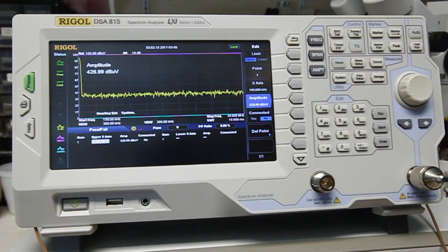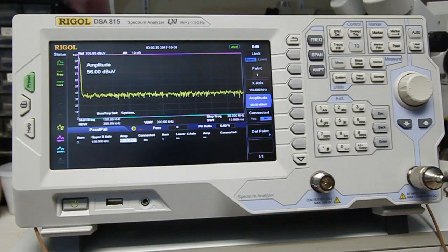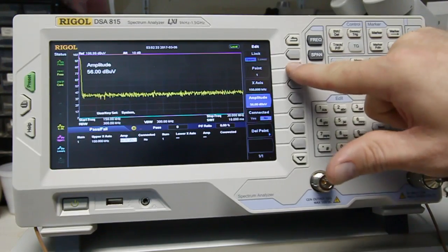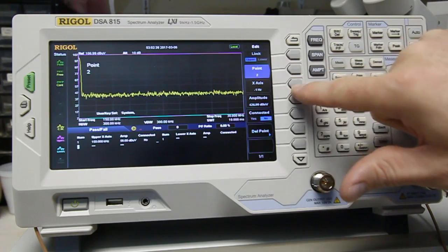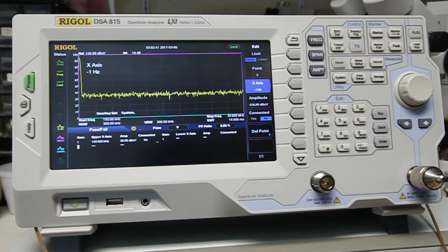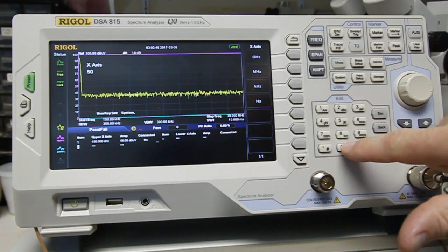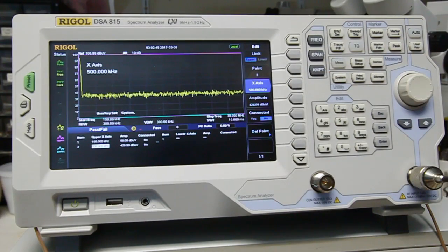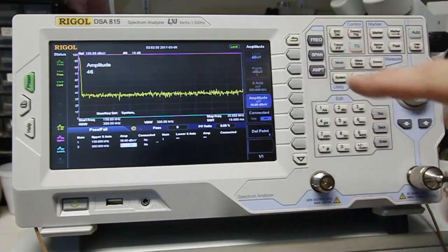And our amplitude that we start out at, we're going to be looking at the average limit. So this is 56 dB microvolts. So we've got our first point in. We're going to go to our second point. The second point of the specification is 500 kilohertz. And it should drop down to 46 dB microvolts at this point.